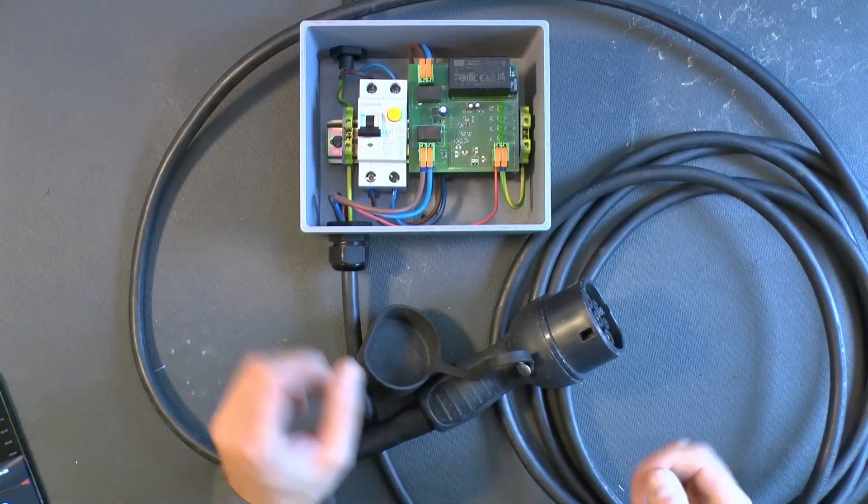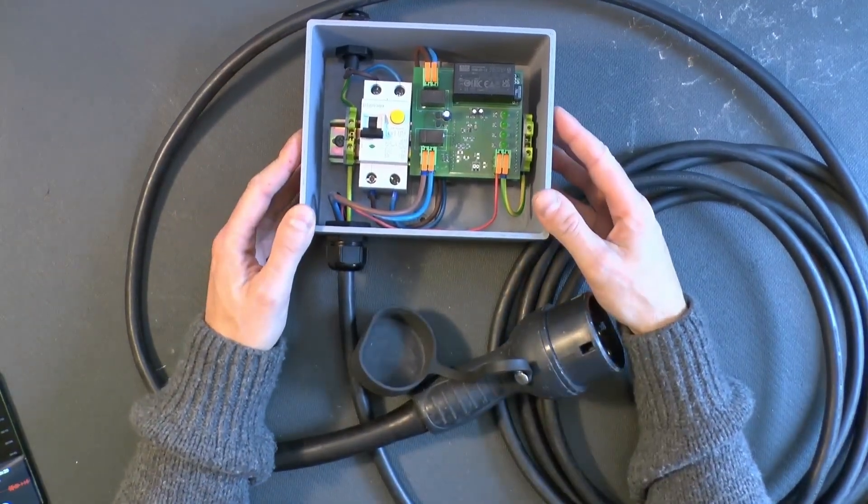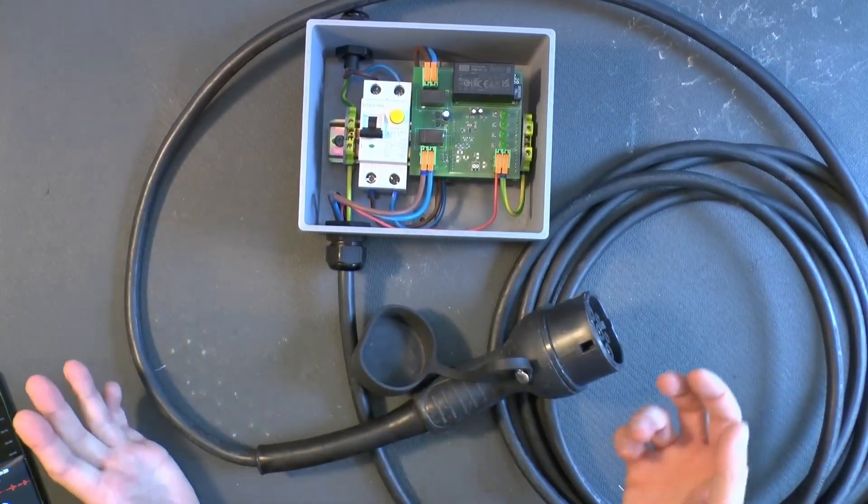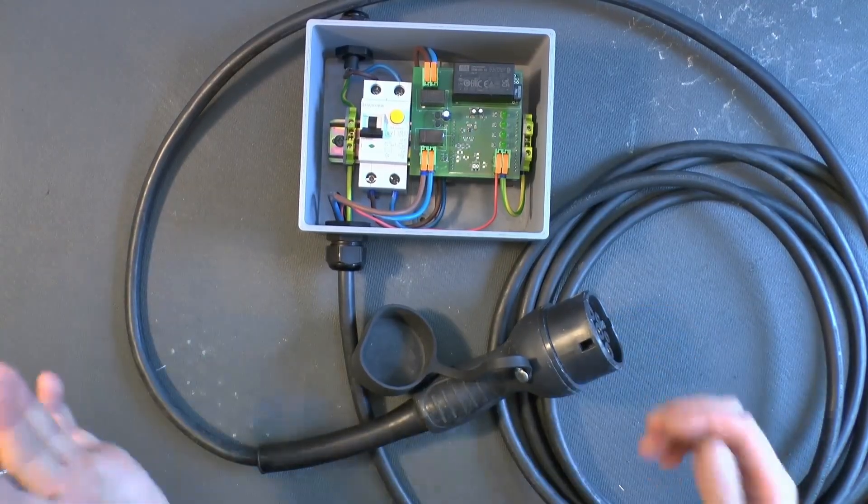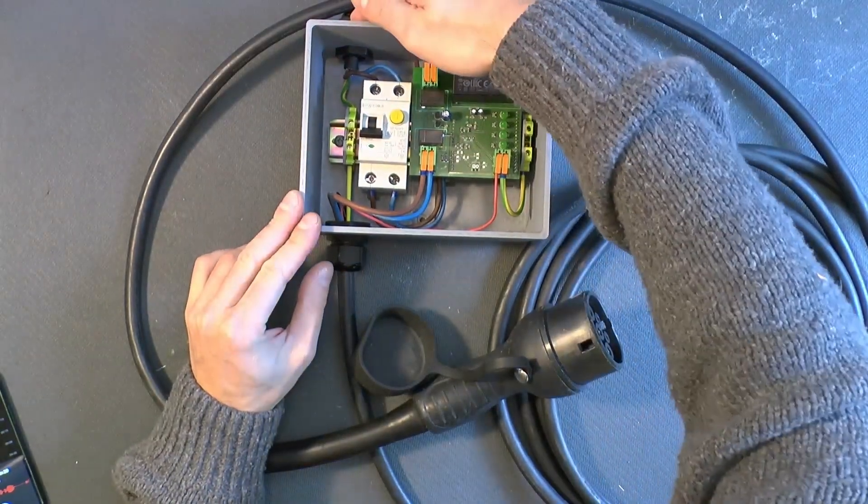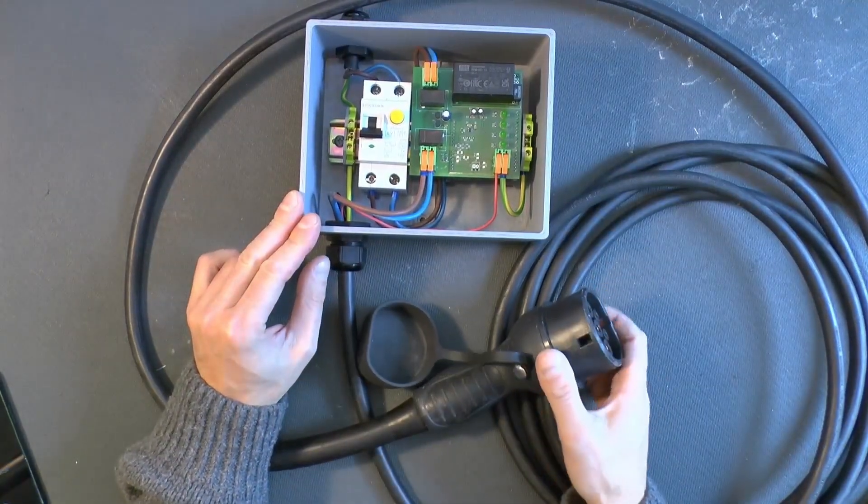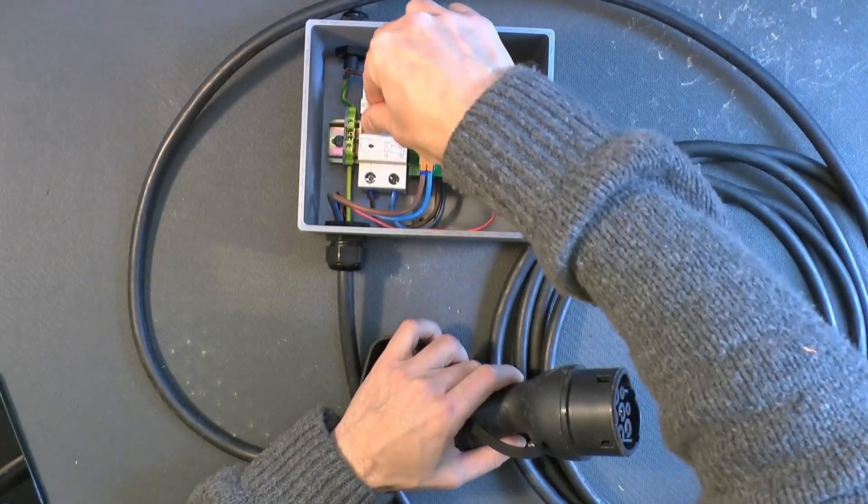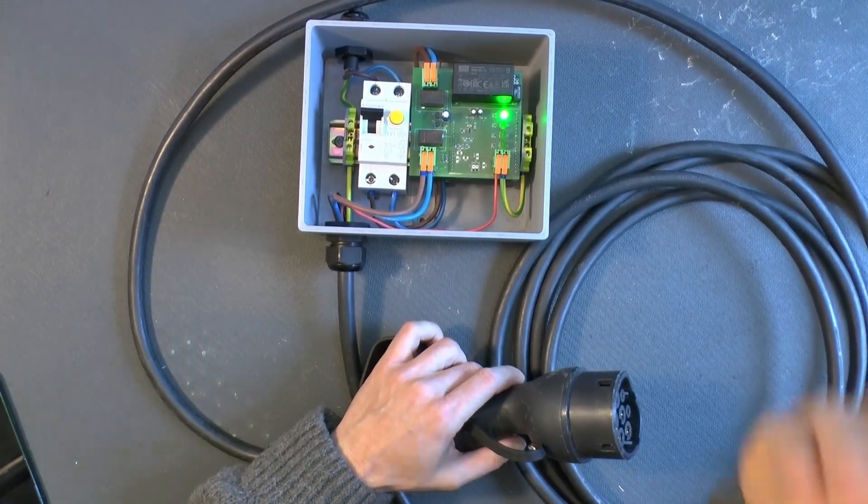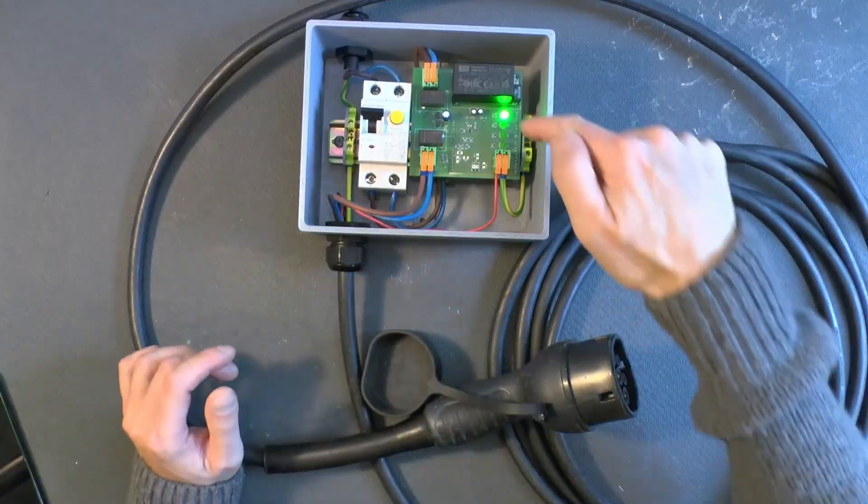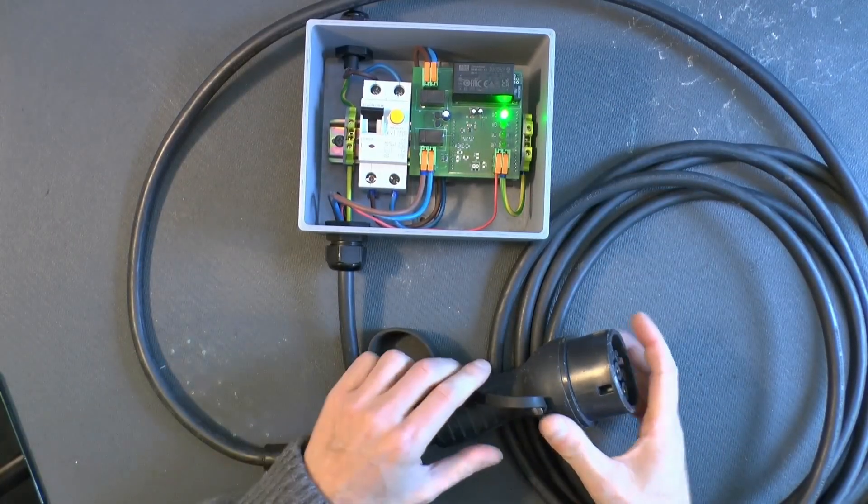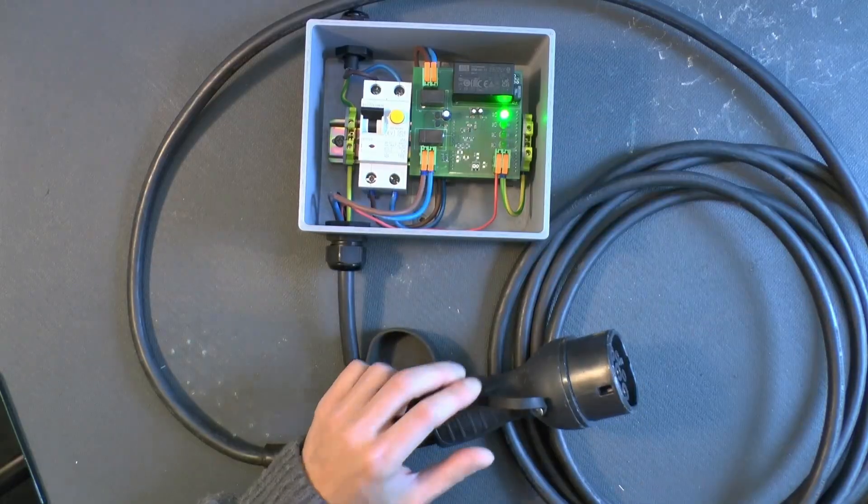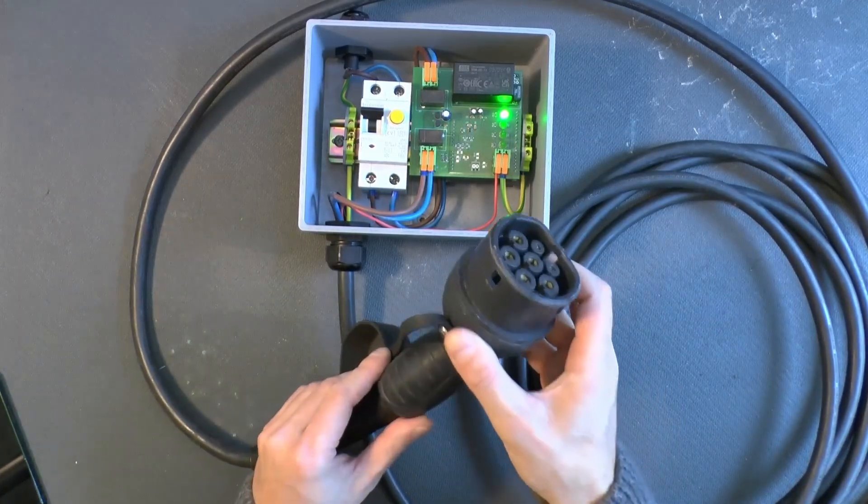So, after everything is put together, it's time to start testing. And it's always a good idea to test progressively. So, first of all, connect power to the charging station. And flip up the RCBO switch. Already we have a good indication that the top LED is on. And then we know that the bottom LED will be on when plugged into a car.